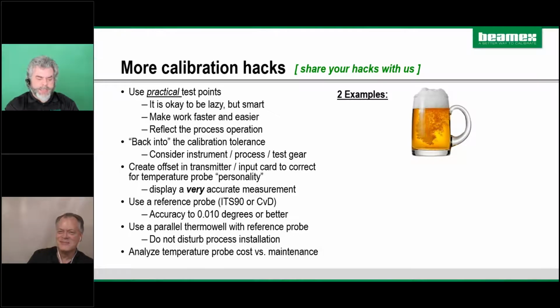So this example was a brewery, and a rather large fermentation vessel. One thing about calibration is that in determining how accurate you need to be temperature-wise, there's a value where your product becomes unusable. If you have a beer and a fermentation process in there, you have to get the temperature up to a certain value in order for the fermentation to start. But as you increase, okay, fine, it's working. But if you go too high in temperature, here's where you kill it. So you have to operate within this range, and that helps you determine how accurately you should be calibrating to maintain the proper temperature.